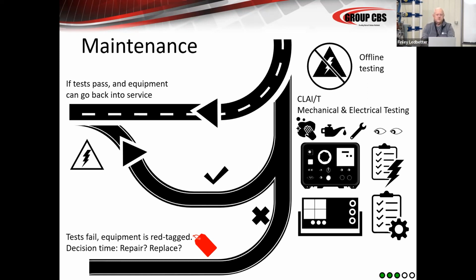Generally, it's accepted that these breakers have sealed bearings and were designed to operate some period of time with very little maintenance. Is that 20 years? Is that 25 years? Is it 50 years? Everybody has a different opinion. But everything has a bathtub failure curve. These breakers do too. When they're young, a lot of them fail. After they go into service a few years, they maintain a very good, robust lifetime. And then at some point, they start to fail again.